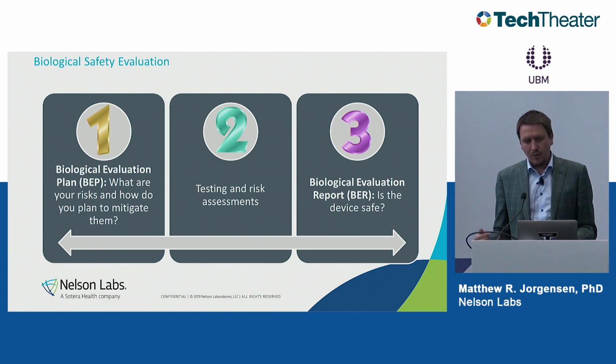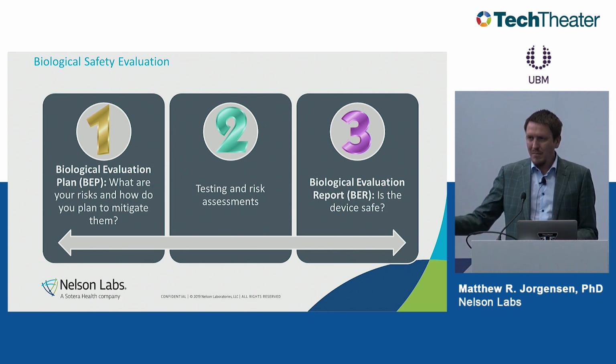So this final report, the biological evaluation report, I found to be really, really important. So there's a lot of packages that cross my desk where the device is great and they mitigated all the risks, everything looks good, but they didn't explain to the FDA why all of this information means that their device is safe. So you've got to bridge that final gap at the end for the regulatory body.